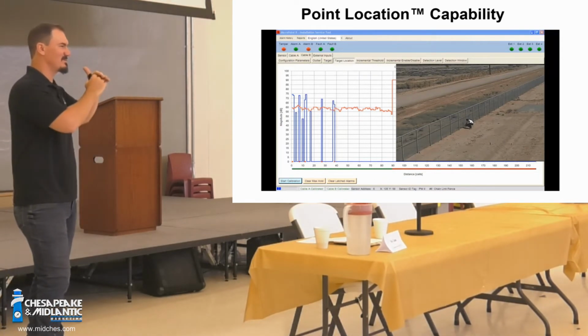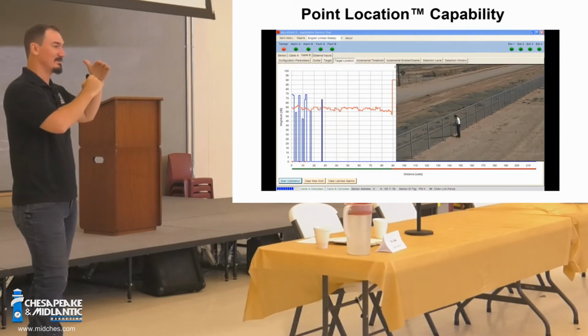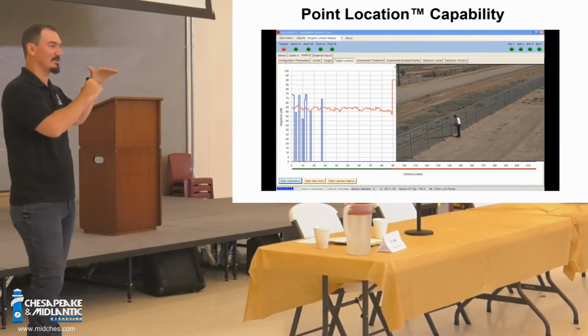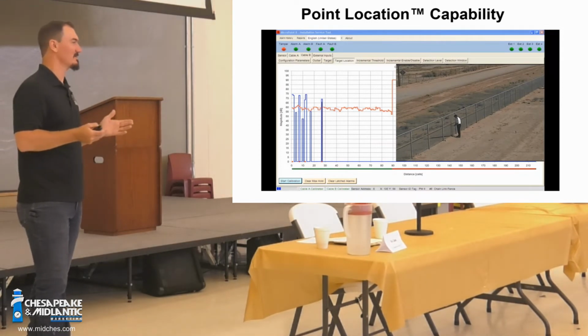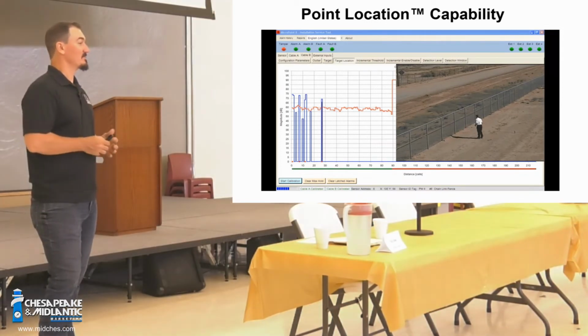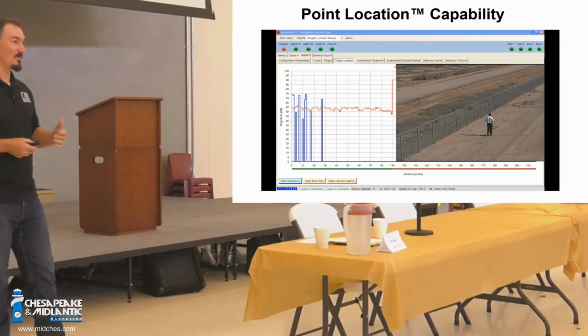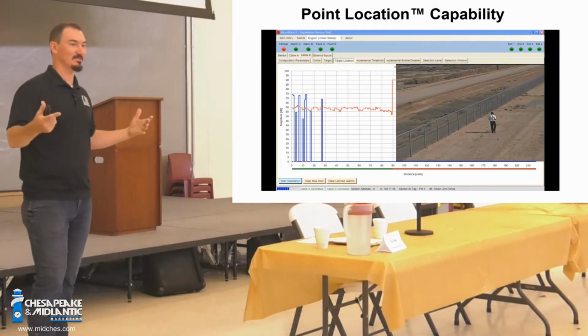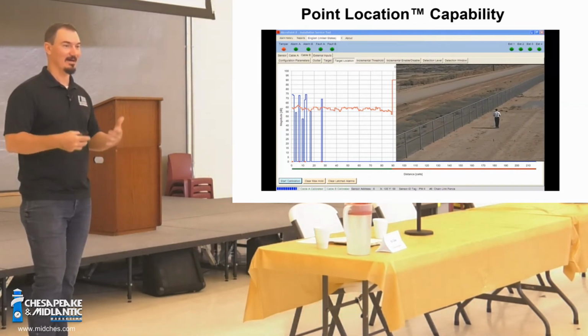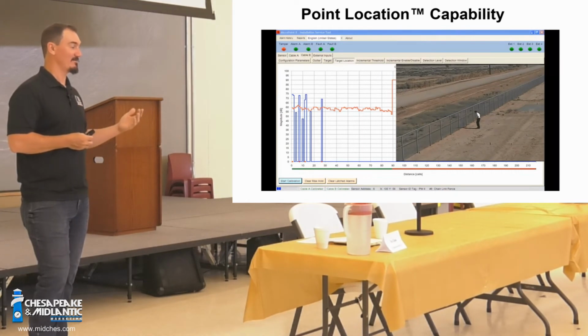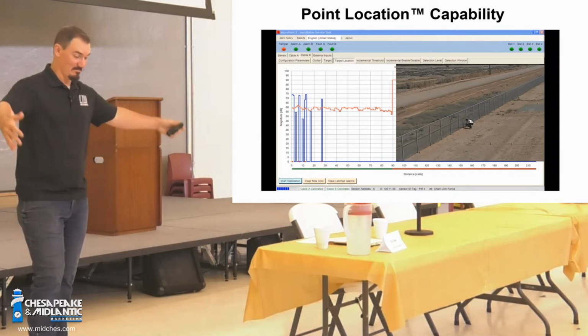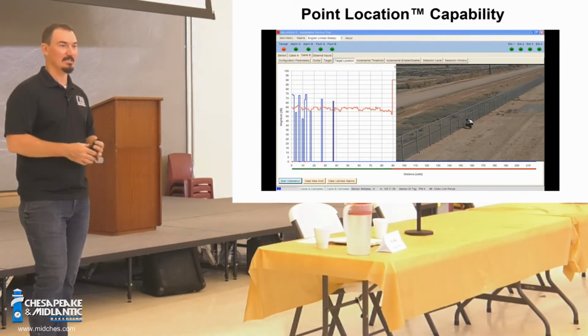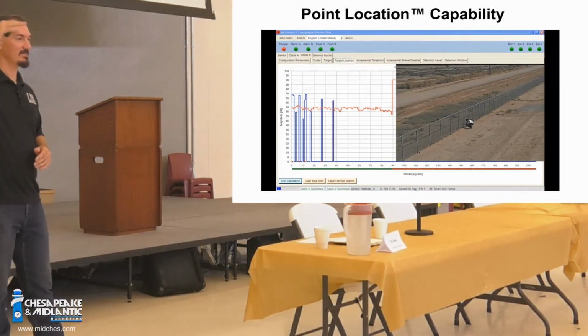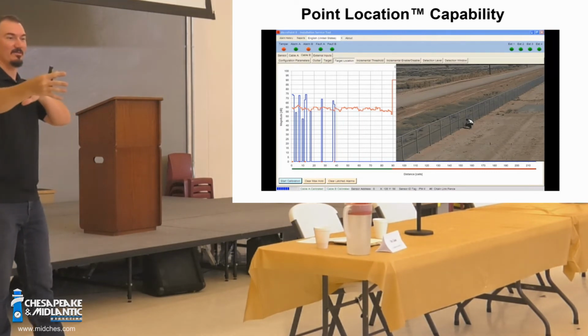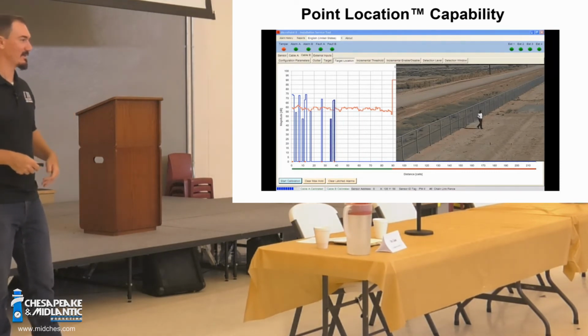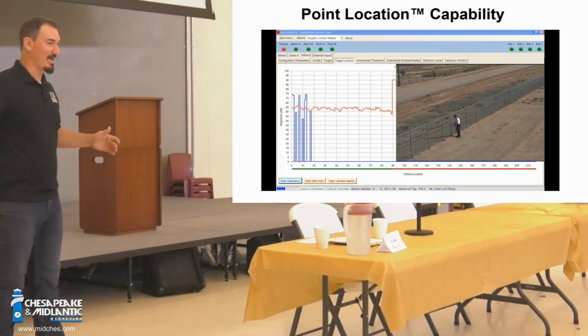Most systems, there's a 6 to maybe 10 dB range from the peak of those cuts to where the actual sensitivity is set. Maybe that. Most are 4 to 6. But there's a balance. As y'all know, anytime you put a sensor out there, there's a chance for nuisance alarms, right? Heavy wind, ice picks up on the fence. In the desert, we have tumbleweeds. Those tumbleweeds can be big. They can be heavy. At some point in time, we will have tumbleweeds stacked 12 to 15 feet high, bunched up against a portion of the fence or against our building when we have the dust storms during our monsoon season. And they're banging against the fence.